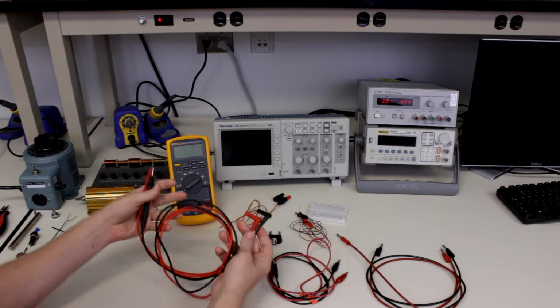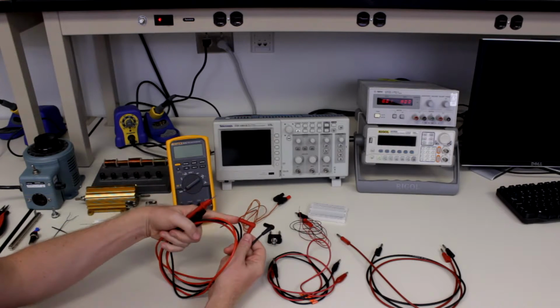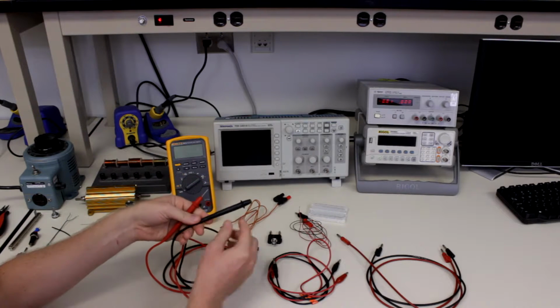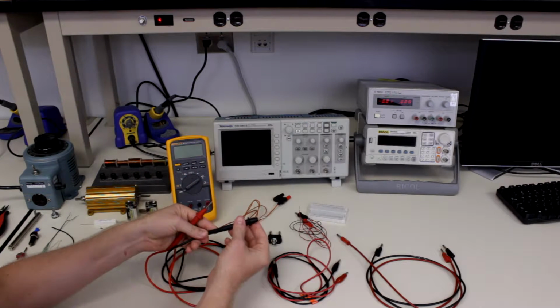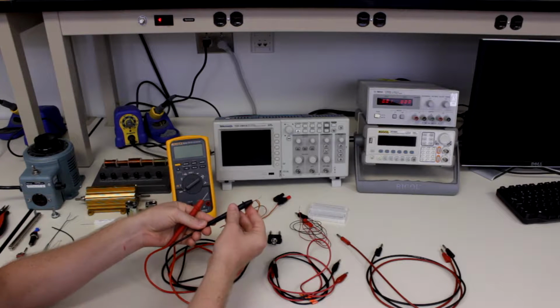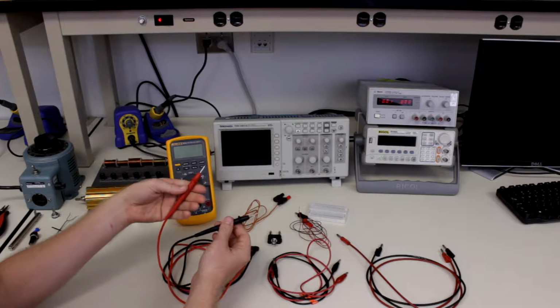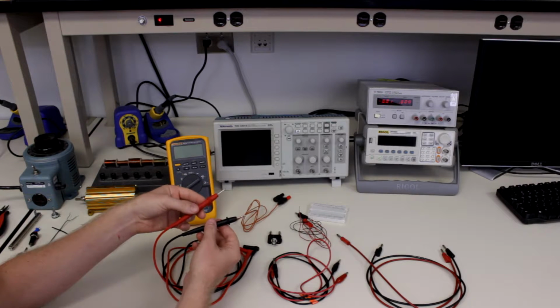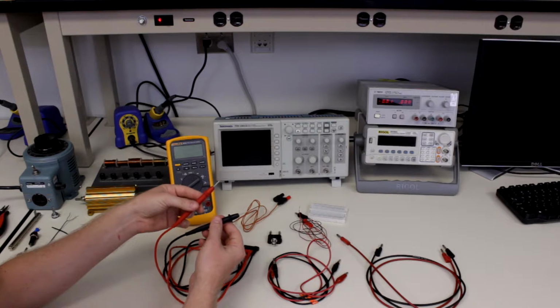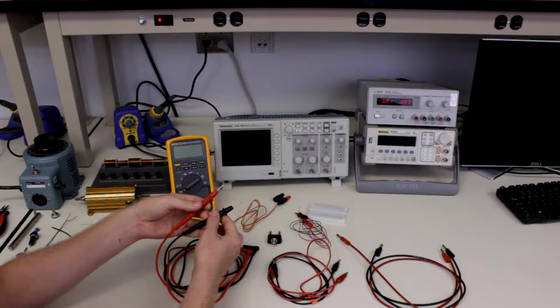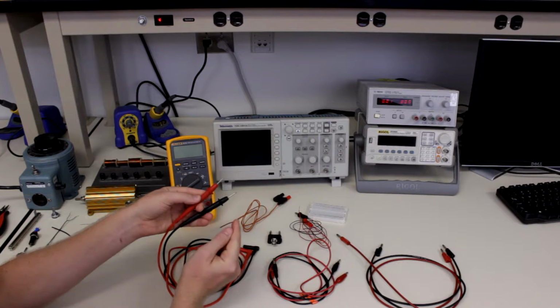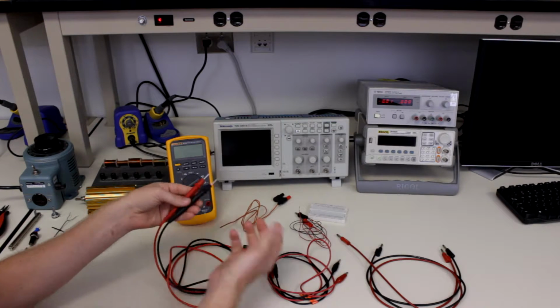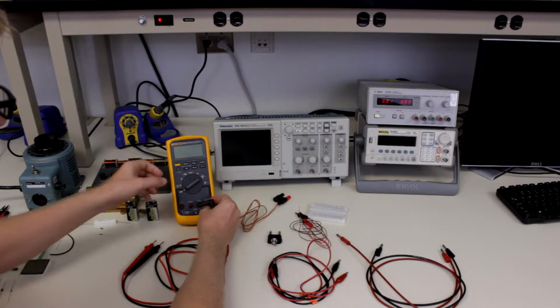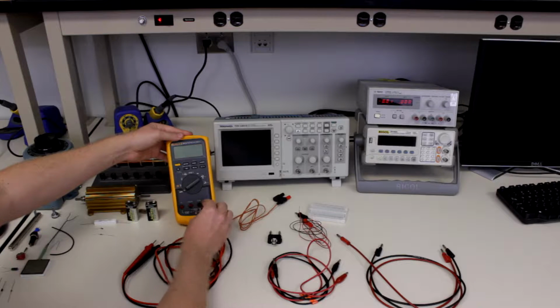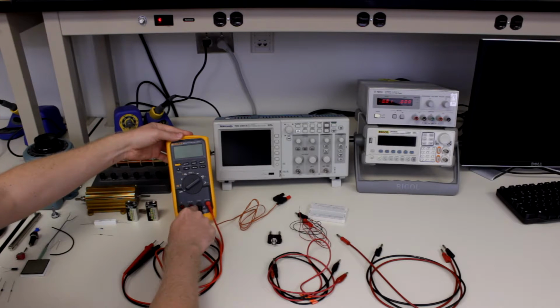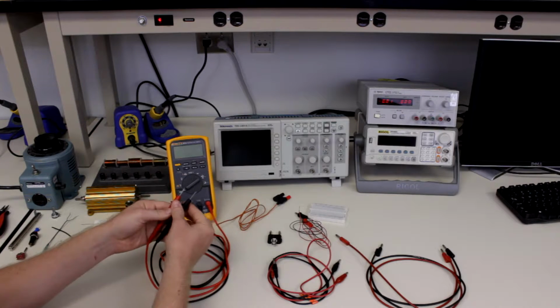But what we're going to start off using are the included probes, which have insulated banana connectors to probes. It's important to use the Fluke probes that come with the DMM because they are Cat III rated to 1000 volts. When making connections to high voltages—OSHA defines high voltage as 42 volts and above, but voltages below that can still be dangerous—don't touch the metal while also making contact with any high voltage. So let's plug these in: the red cable to the rightmost terminal and the black cable to the COM, or common, terminal, and make some measurements.